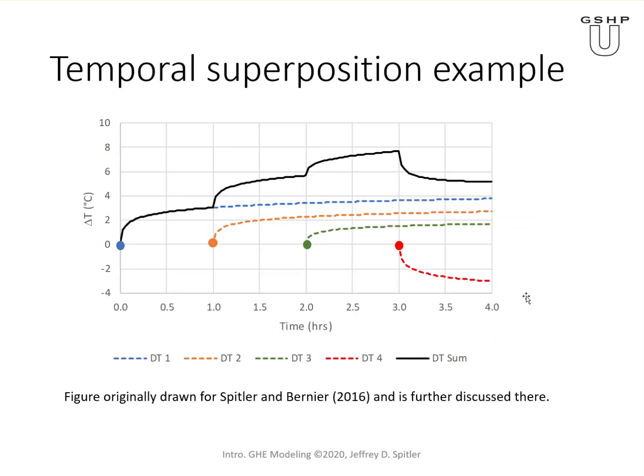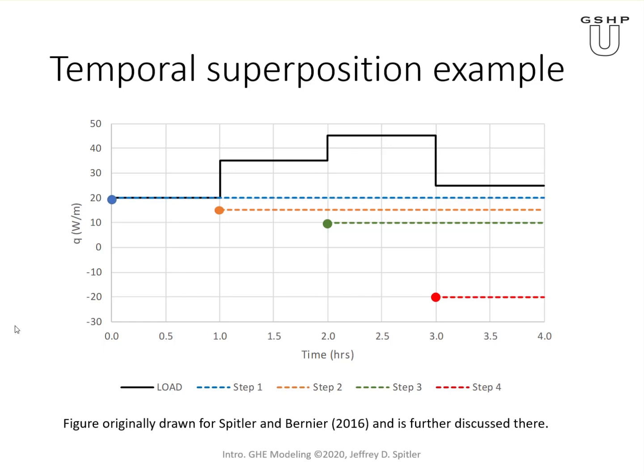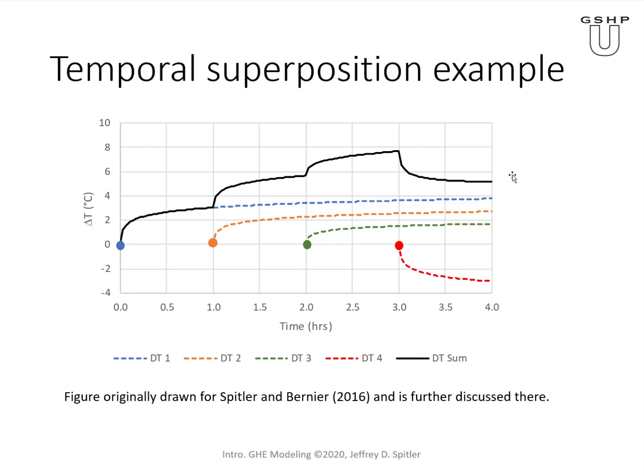Using the line source — or another approach — we calculate the temperature response, specifically the delta T at the borehole wall, for each of these step functions. The black line shows the overall response when all contributions are summed together. The blue dashed line is the response due to just the first pulse of 20 W/m, then we add the response to the 15 W/m pulse, the 10 W/m pulse, and the negative 20 W/m pulse. When added together, we get a sawtooth-type profile that tracks the original load steps.